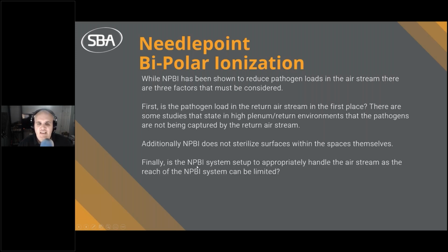And then finally, is the NPBI system set up to appropriately handle the airstream, as the reach of the NPBI system can be limited? In extremely long or large systems, the ions, from everything I've read, can disperse pretty rapidly. So if you have a long run, you may have to lay out your system differently because it's not going to handle a long run. So be cognizant of where you place the system within the airstream. All right.